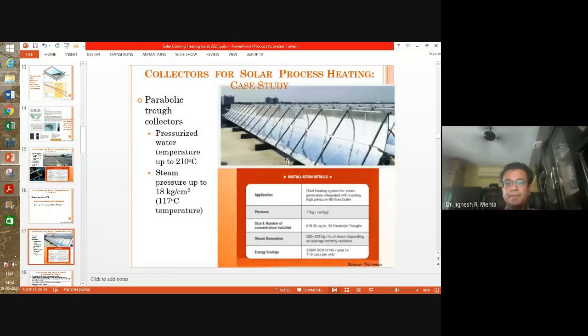So now I'm talking about the other type of collectors which may be used for again heating. And when you talk about cooling, actually the same collector which is used for heating may be used, right? Because finally you are converting heat into cooling with the help of a refrigeration system, right? So then another one is the parabolic trough type of collector, and this should be used when you need higher temperatures, right? You should not use the concentrating type of collectors for low temperature applications, because at low temperatures they will give you lower efficiencies and the investment cost also would be higher.